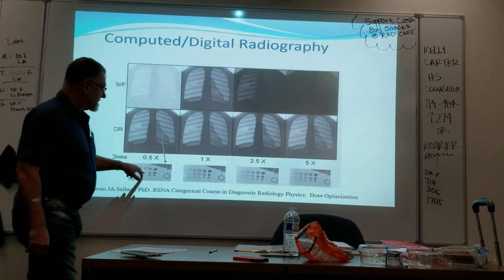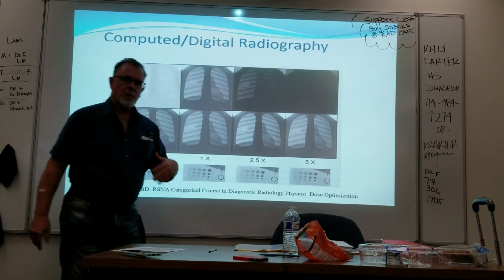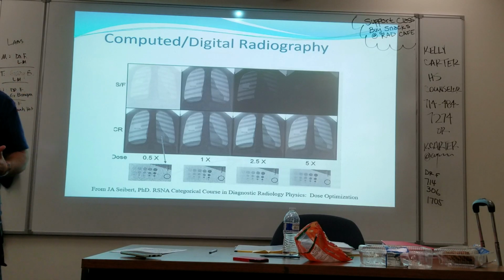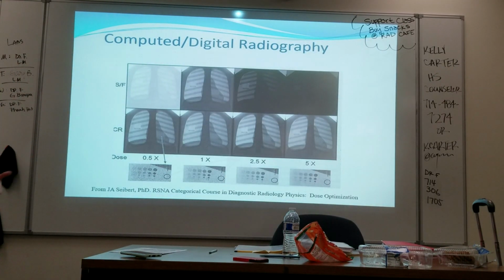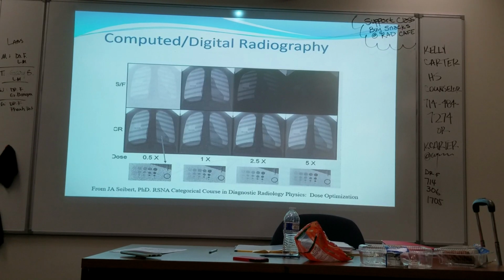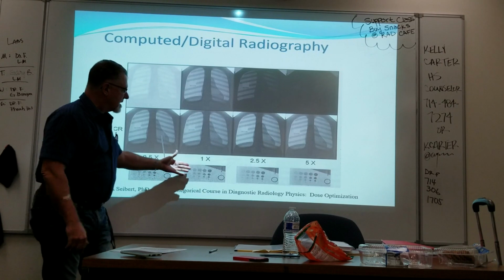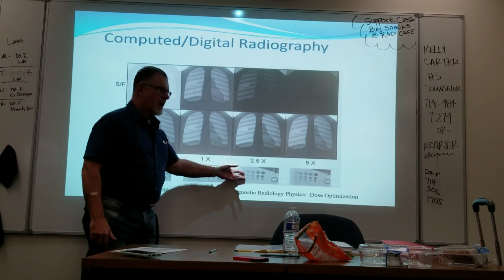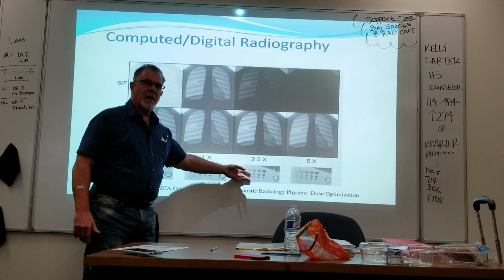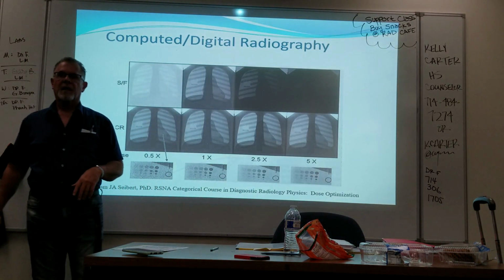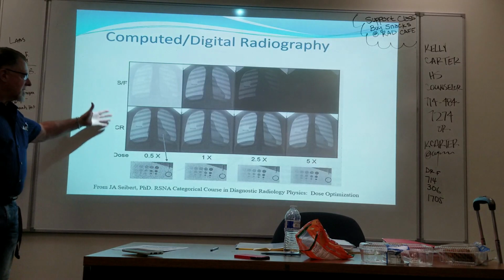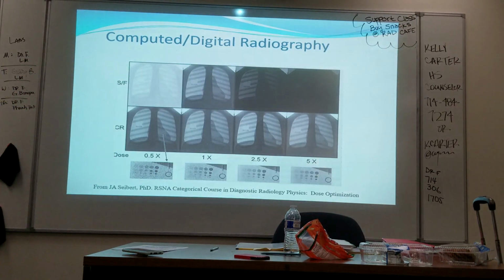But in testing, you also want to see what it actually looks like, because at some point, when you're trying to establish a new technique or a new procedure, you can't do it on patients. Okay? You can't make patients your test phantom. You need to use phantoms to determine at what point we get sufficient low contrast visibility that's acceptable without overdosing patients. And that's what phantoms in your quality assurance program can do. It can give you a starting point for new procedures, or a way to evaluate if your current performance is what it's supposed to be.